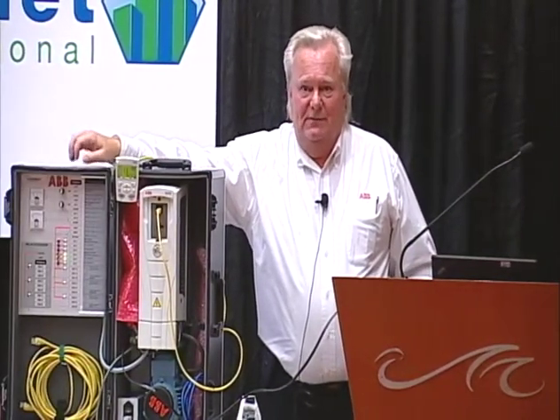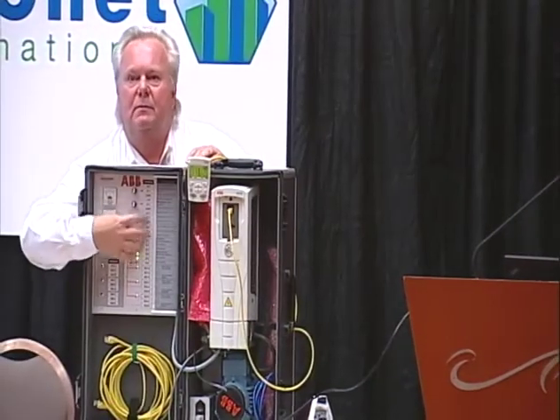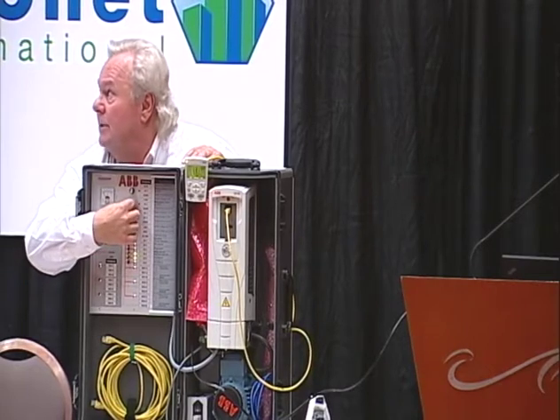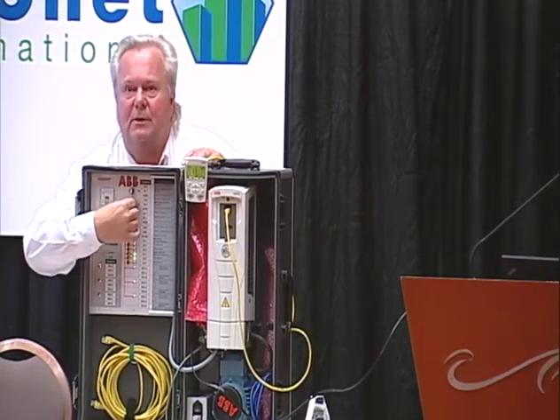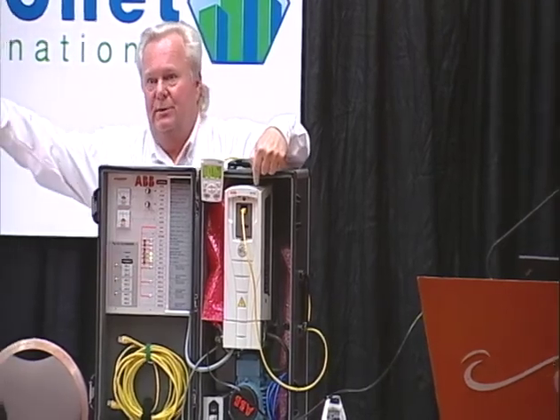Now the bad thing about this mode of operation, of course, is if I lose communications, I'm staying at that last command. So in 2004, it hit us and we said, we've got extra power in the microprocessors on board our drive, so we put in another PID loop. So the scenario on the chill water valve is that the chill water temperature sensor is wired back to the VFD. Over BACnet, I give it the set point, and then as I vary my feedback, which is wired into analog input 2, I control that analog output to control the chill water valve. So now the PID loop is here, rather than in the building automation.